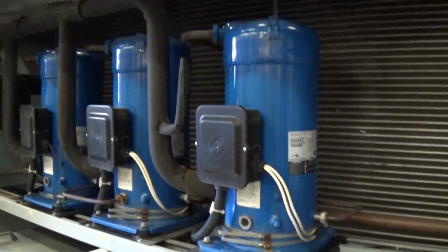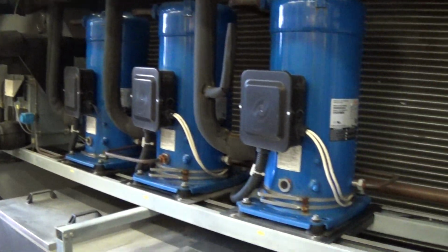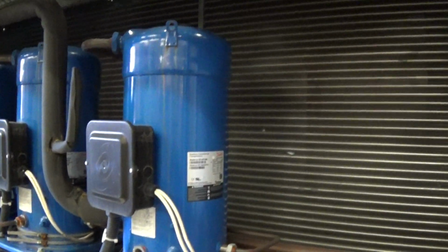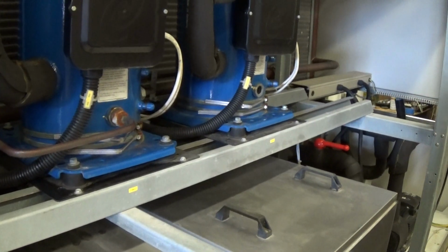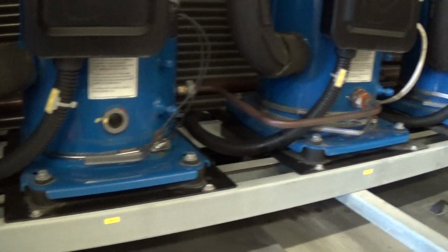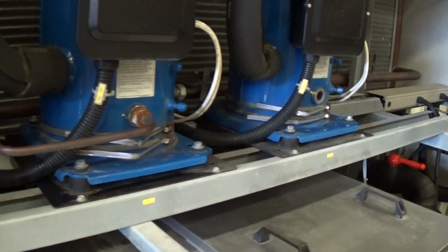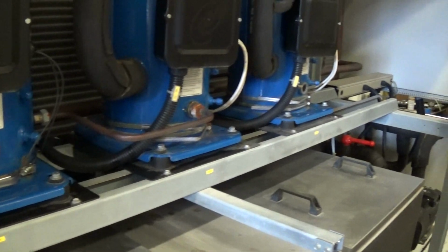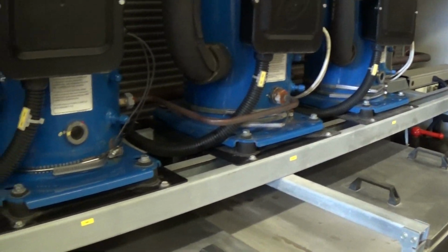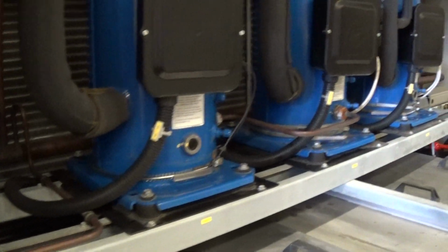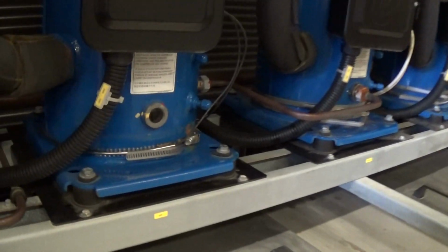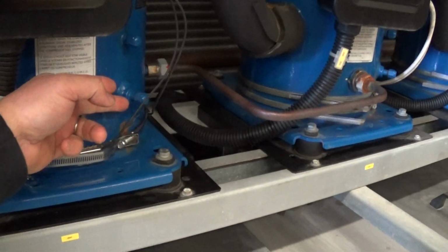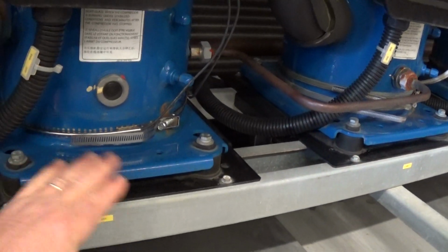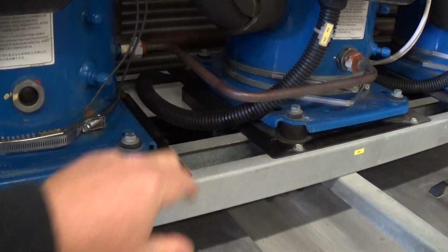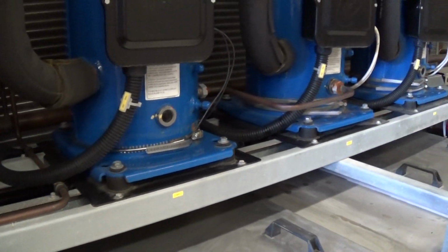We have 3 Danfoss scroll compressors, R407C, approximately 13 horsepower each. The compressors all have functioning and checked out heater bands on them. When you first get this chiller, you should have power to the control cabinet, and we'd like to see these on for at least overnight, ideally 24 hours, to get the refrigerant up to temperature. It has very little to do with the ambient temperature outside. You want these warmed up overnight, and the bottom of the compressor should be warm to the touch. The actual heater band itself will be hotter to the touch. You can do the tap test, but don't press your finger on there.